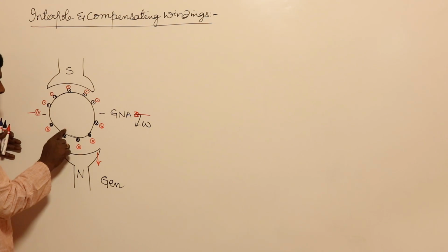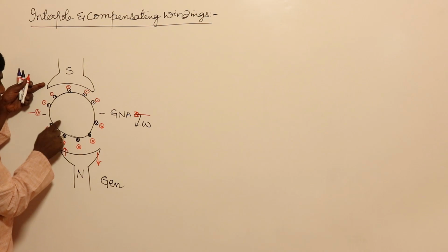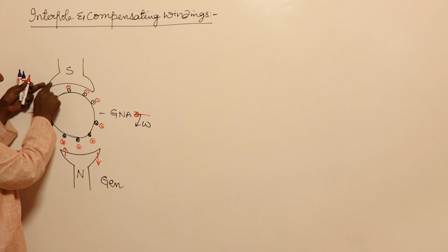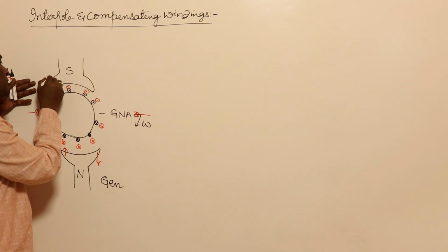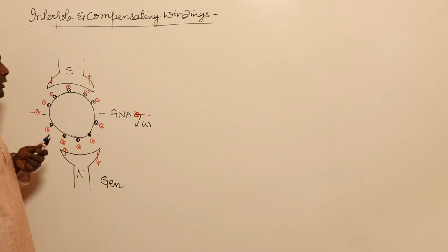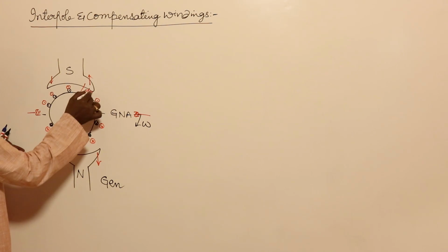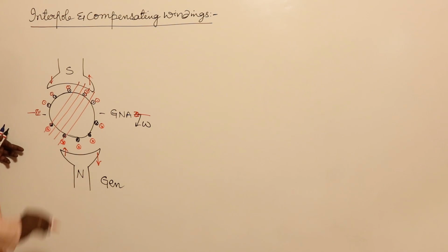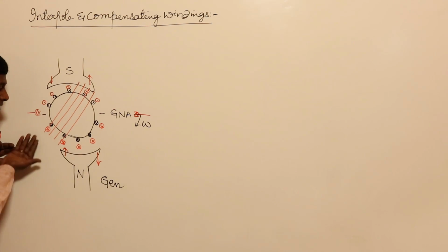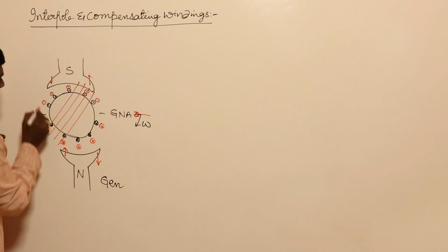Now here also, if I am rotating like this, this pole tip is leading me, so this is going to be the leading pole tip. Here flux should be reduced, and here flux density should be increased. Such that what will happen? My resultant flux will be in this direction, so my flux will take a turn from here and go like this. So the MNA got shifted.